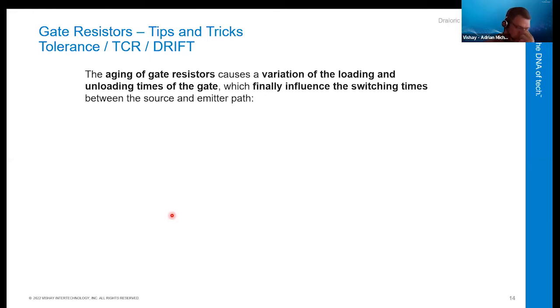Now we have to take a look at what happens with the resistance value during the application - during the heat, during the pulses we see, there's a phenomenon we have to look at: the drift behavior itself. So finally, you selected a resistance value of maybe 2 ohm, and over the lifetime of the application, that 2 ohm is drifting to 3, 4, 5, or drifting down to 1 or 0.1 ohm.